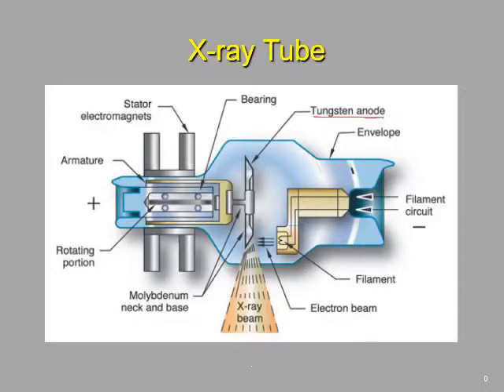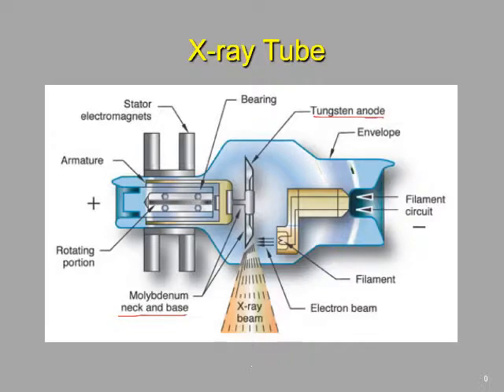You'll notice there is a separate material — molybdenum — for the neck and internal portion of the base. Why do we do that? It is more lightweight, yet still has a very high heat tolerance, which allows us to rotate this anode at high speeds with a decreased amount of mechanical energy required.